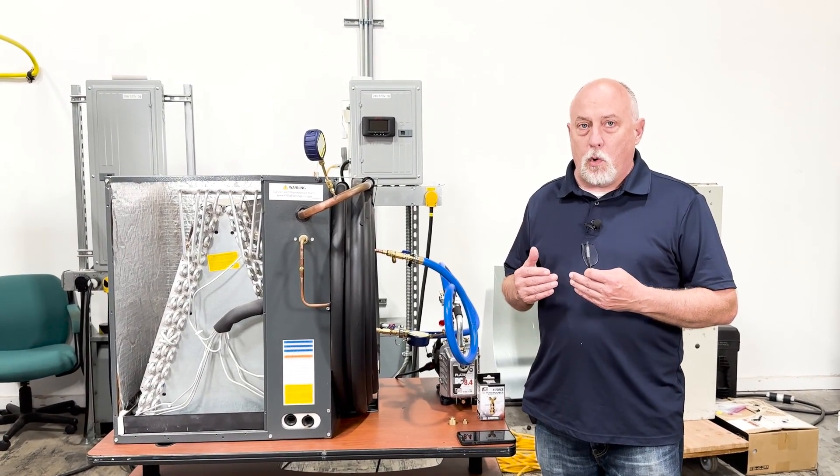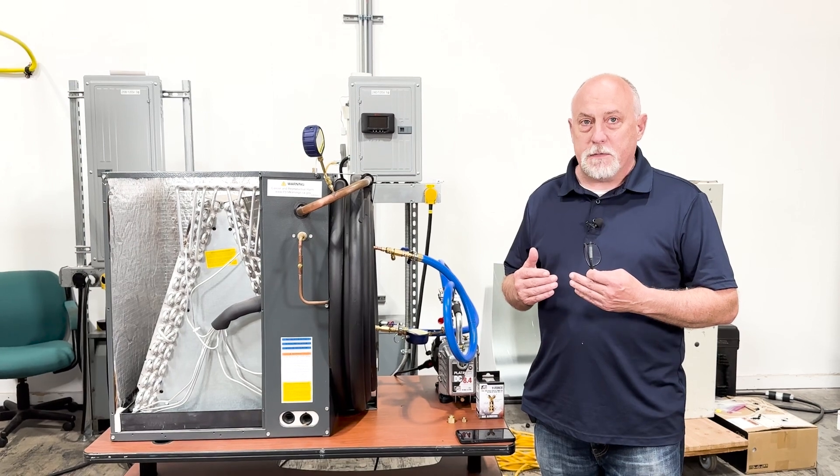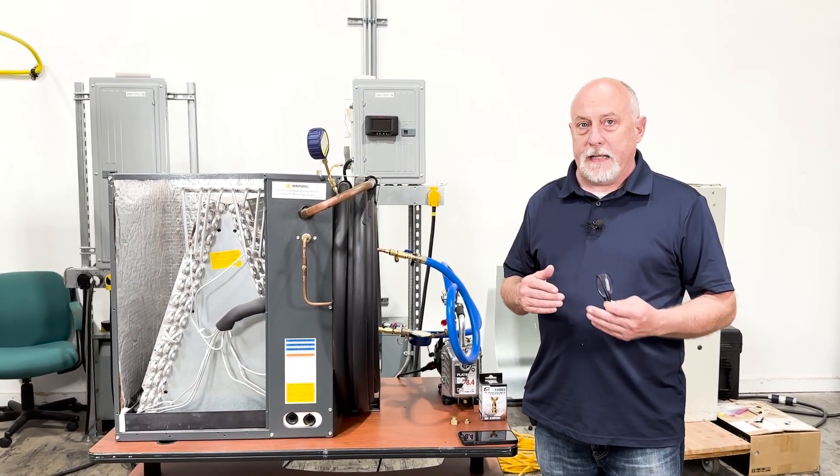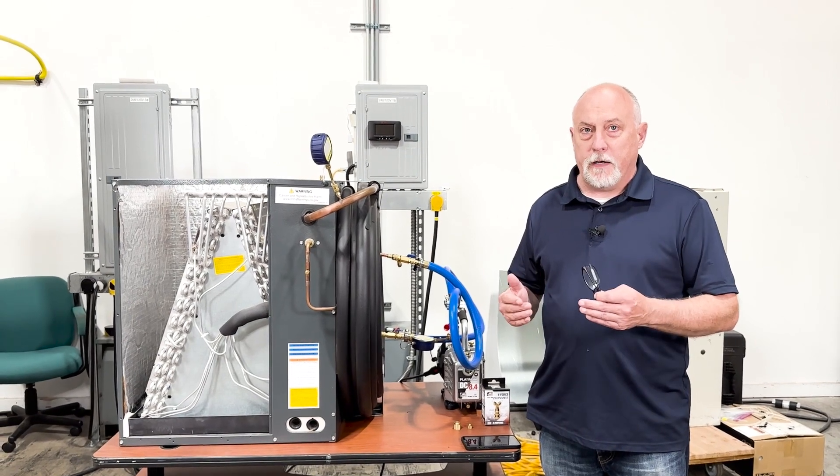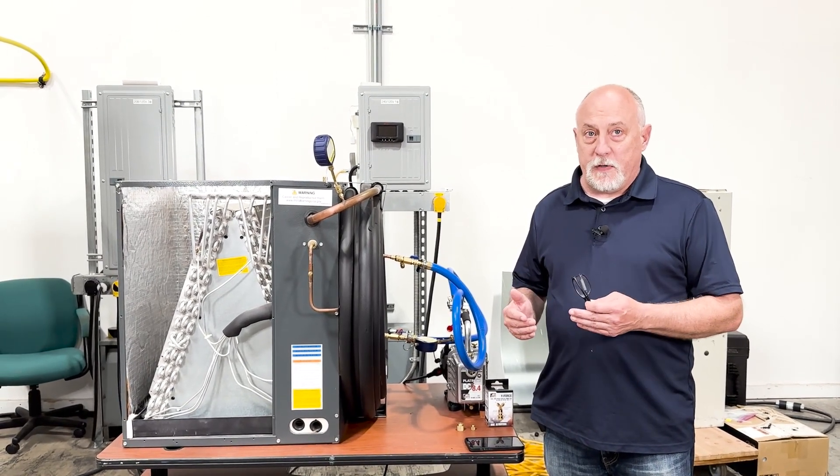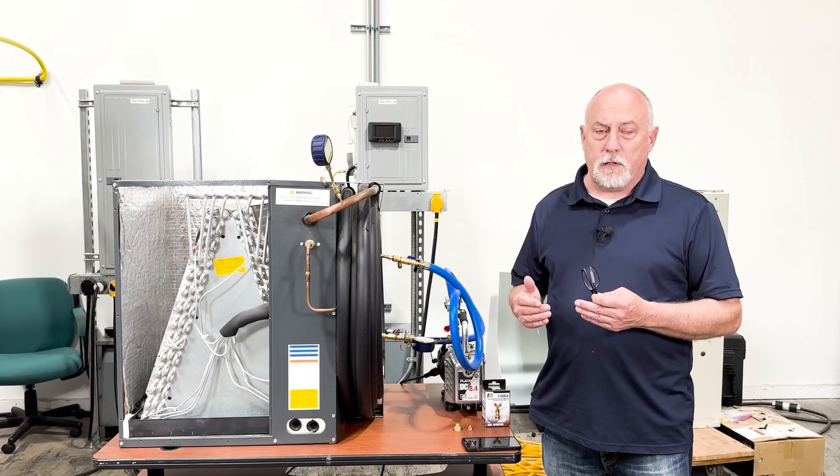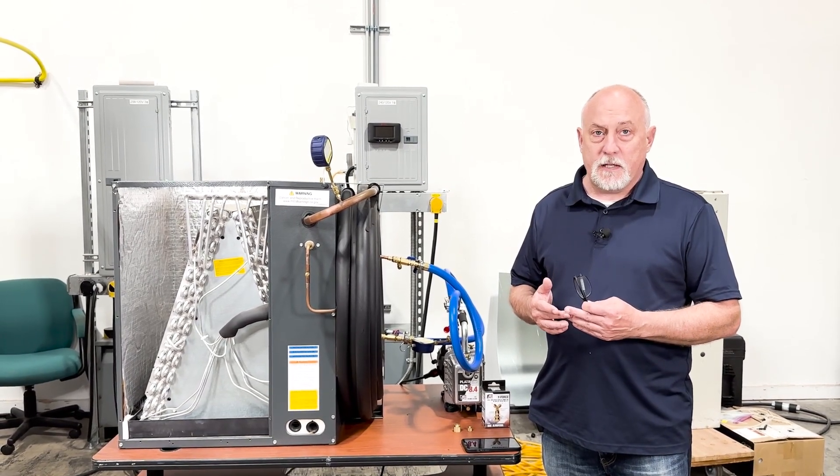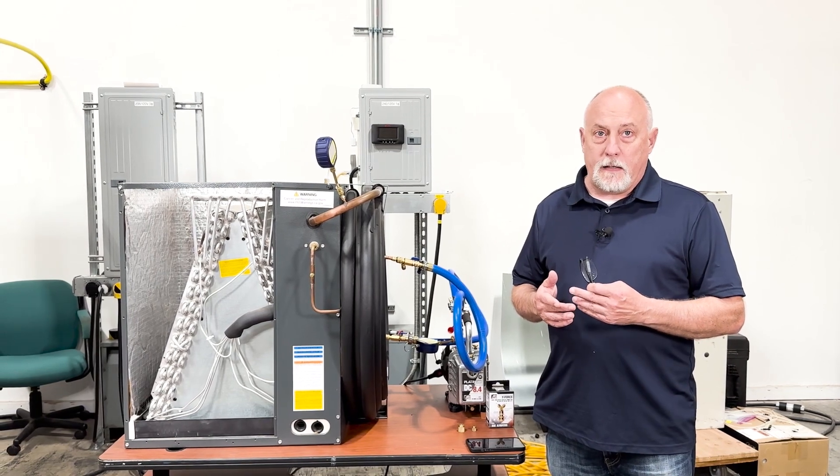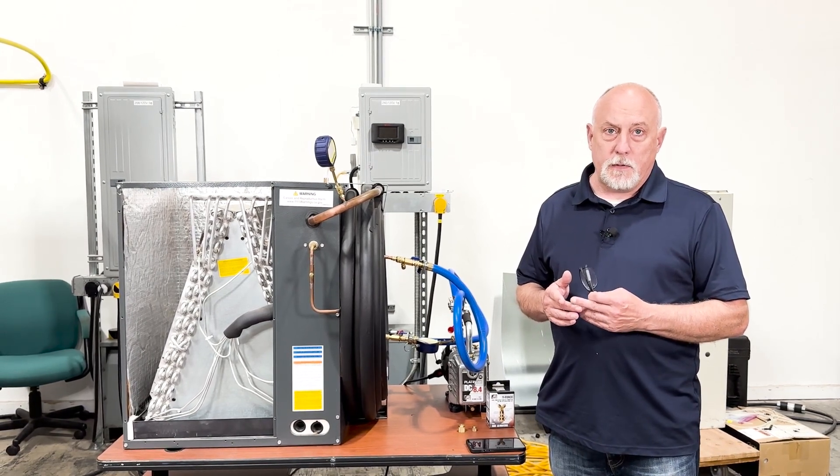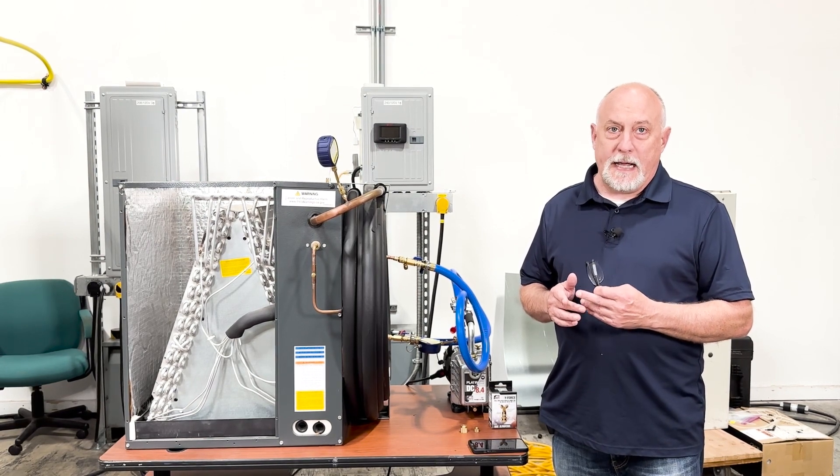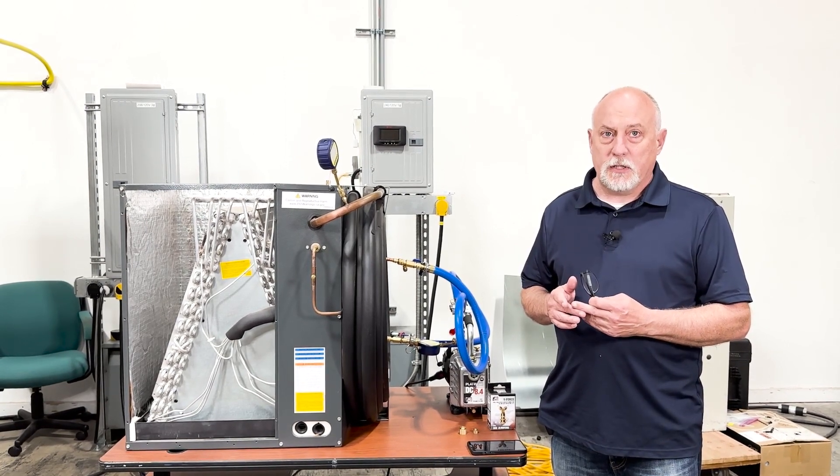This is especially important when we're talking about heat pumps, because now we have a system that's operating in the winter and the outdoor coil, which is now the evaporator, can operate far below freezing. That moisture could have really detrimental effects to the system, either freezing up in the system or because we're running higher head pressures due to heating, we have a chemical factor that can make acids and sludge and really reduce the life of that heat pump.